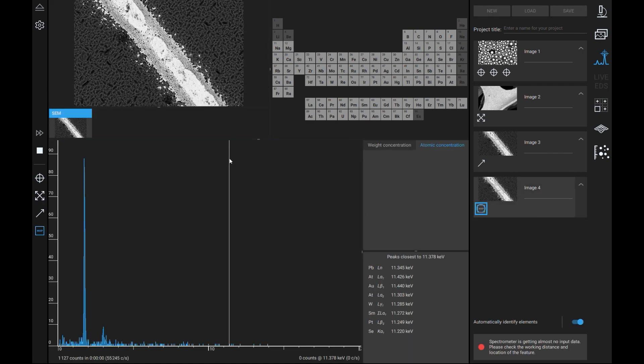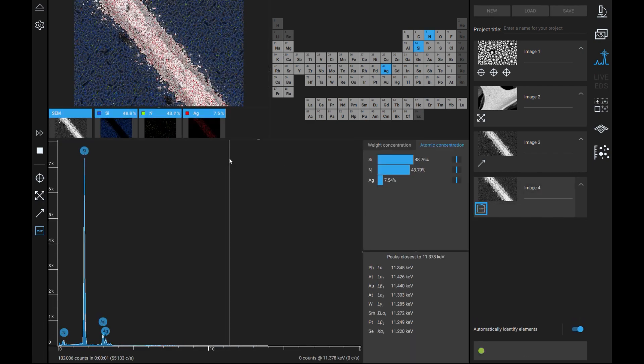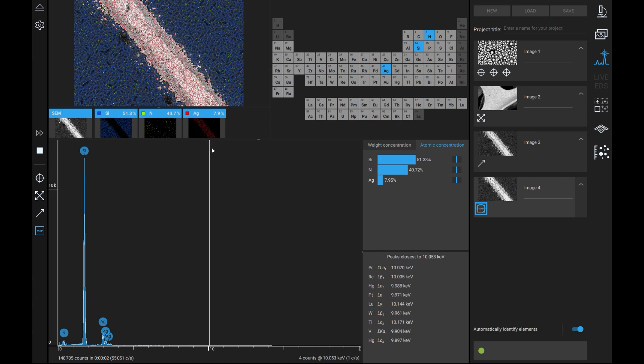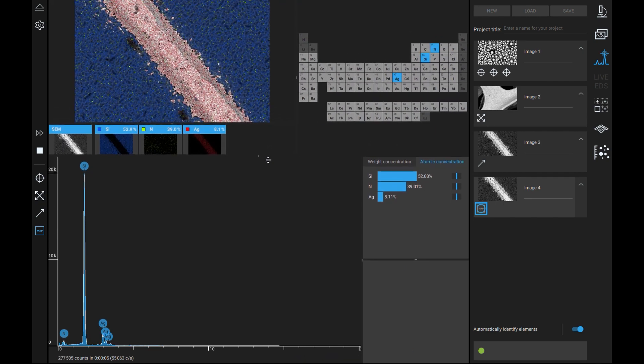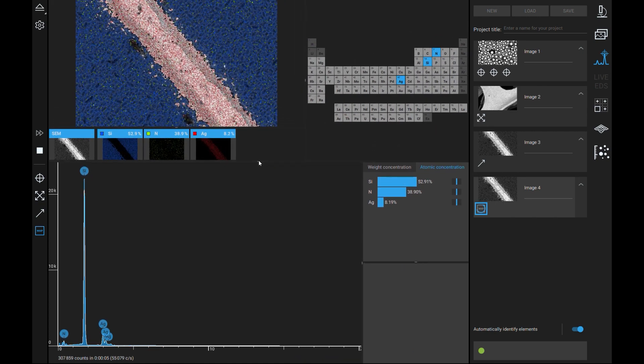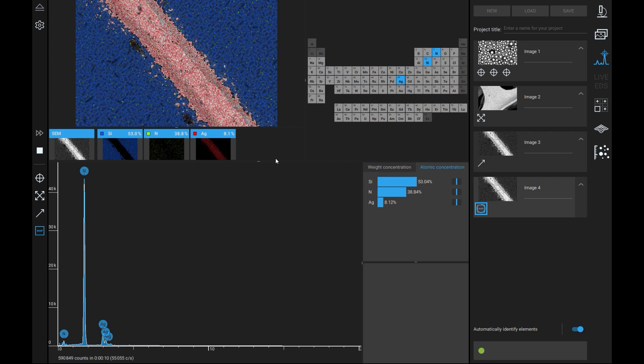EDS mapping displays the exact location within an area where the software identifies an element designated by different colors. Similar to region analyses maps can be drawn by left clicking and dragging over a specific region of the image or by simply left clicking the image. Once drawn the software will start to populate the image with colorful pixels each of which indicates a signal from a certain element. The result of map analyses is high resolution colorful images showcasing the elemental makeup of an image or region.